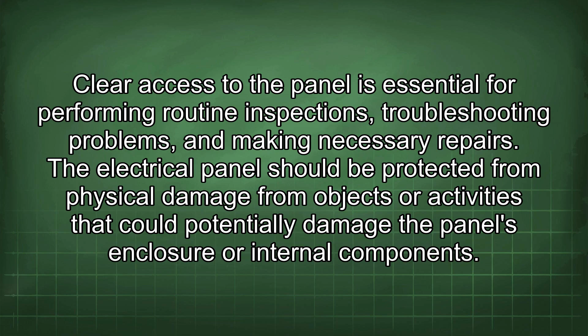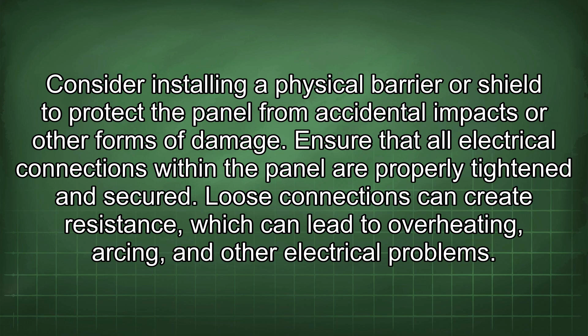The electrical panel should be protected from physical damage from objects or activities that could potentially damage the panel's enclosure or internal components. Consider installing a physical barrier or shield to protect the panel from accidental impacts or other forms of damage. Ensure that all electrical connections within the panel are properly tightened and secured. Loose connections can create resistance, which can lead to overheating, arcing, and other electrical problems. Periodically inspect the connections to ensure that they remain tight and secure.